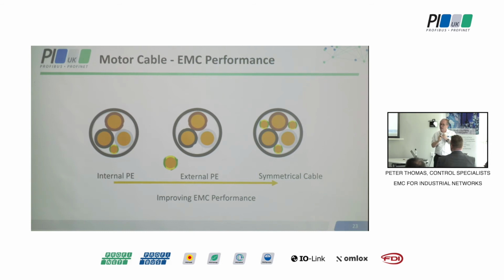And you will find that different drive manufacturers recommend different things. For example, one manufacturer will say, this is what you want: we want a shield. You can have an armour on there for mechanical protection, but we want a shield. Another reputable one says an armoured cable will be fine. So what do we do? We need to follow the guidelines, but I know for certain when I've discussed that with EMC consultants, they've raised their eyebrows as to whether that is actually going to be good enough.